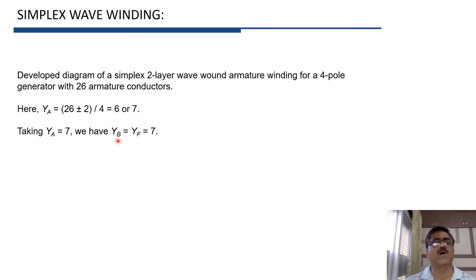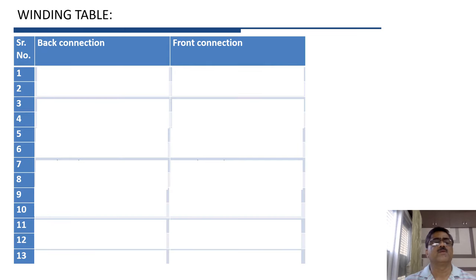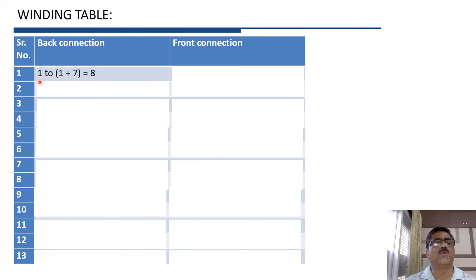Back pitch YB and front pitch YF are both equal to 7. The front side is the commutator end and back side is the other end. Starting from conductor 1: on the back side, conductor 1 is connected to 1 + 7 = 8. Then on the front side, conductor 8 is connected to 8 + 7 = 15. Then 15 is connected to 22.